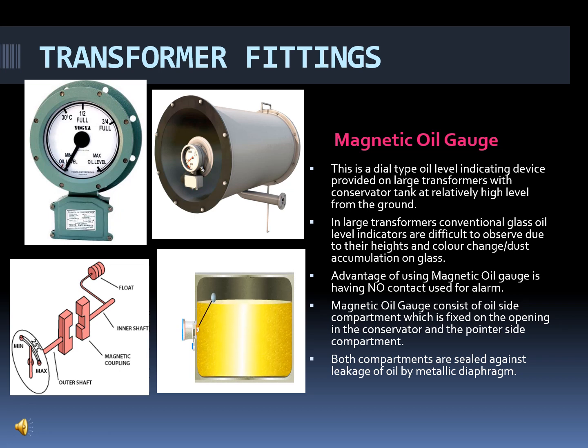An advantage of using a magnetic oil gauge is that it also has a NO contact. The NO contact can be used for alarm or trip as per the customer requirement. And the magnetic oil gauge consists of 2 compartments. One is the oil side compartment, and the other is the pointer side compartment. Both compartments are sealed against the leakage of oil by a metallic diaphragm.